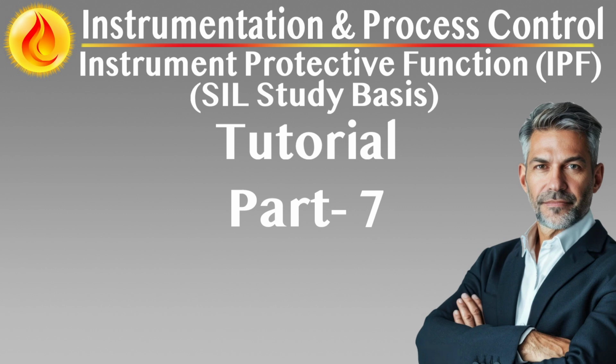Failure investigation and response. If a test reveals failure, the root cause must be investigated, corrected, and documented before the IPF is returned to service. Performance trending. Over time, test records should be analyzed to identify trends in reliability, leading to better maintenance planning and potential design improvements.